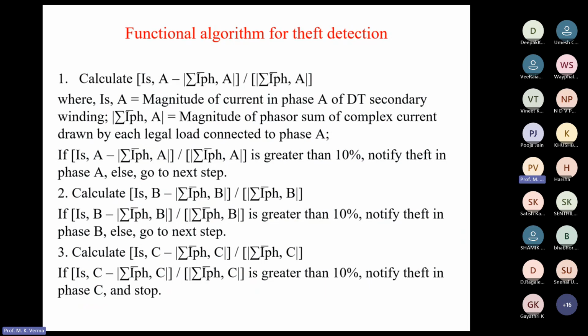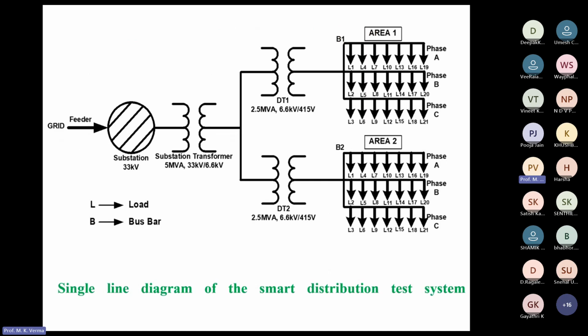Then for theft detection, he developed an algorithm based on the readings of different meters, and naturally, if there is theft, that will not be measured. So he measured the current at the control center: what is the current in that phase, and what is the sum of the currents of different consumers. If that is matching, then it means there is no theft. If it is not matching, somewhere there is theft. Based on that, he developed the algorithm, and the case studies were performed on this system.